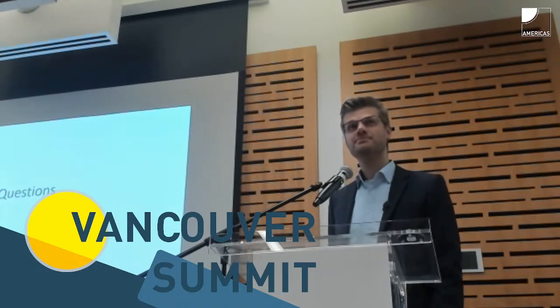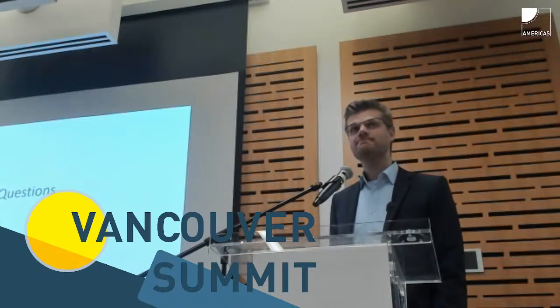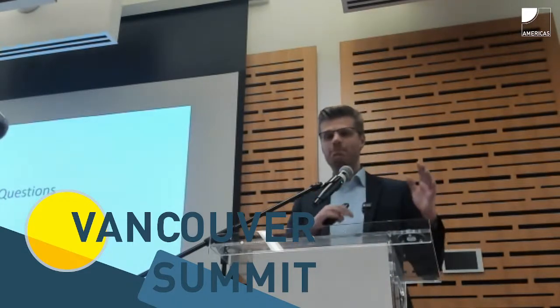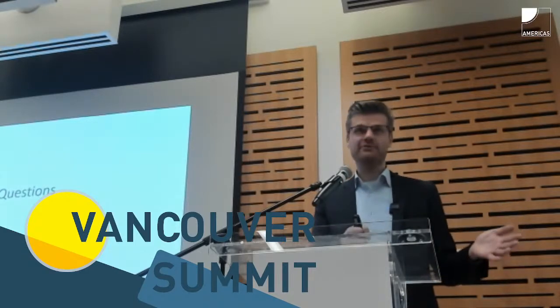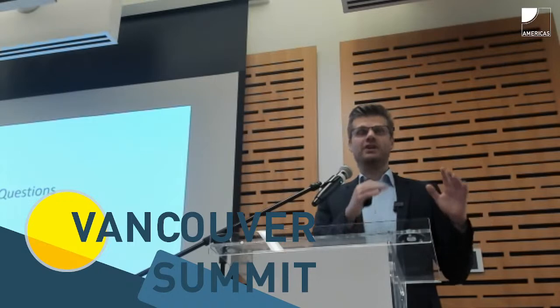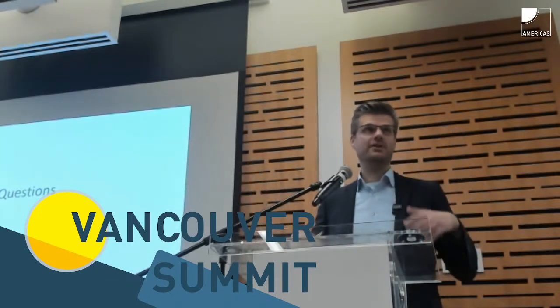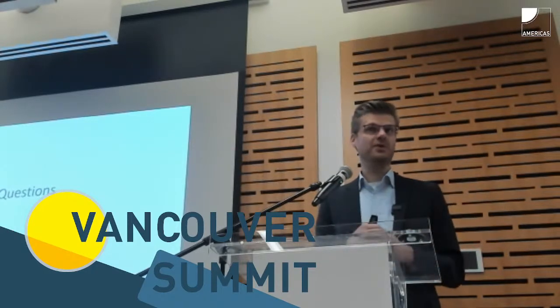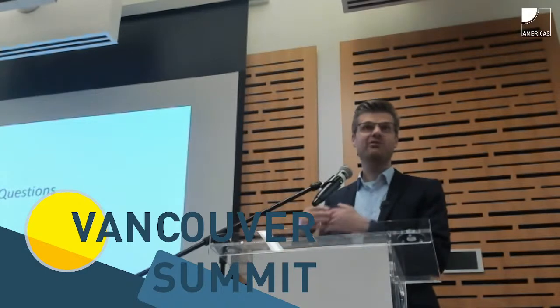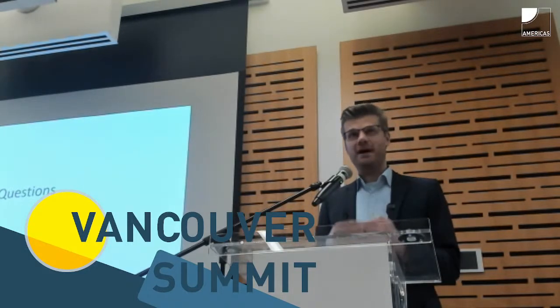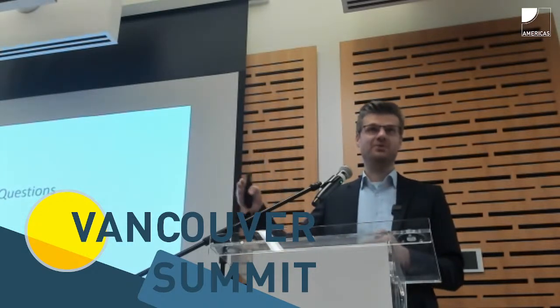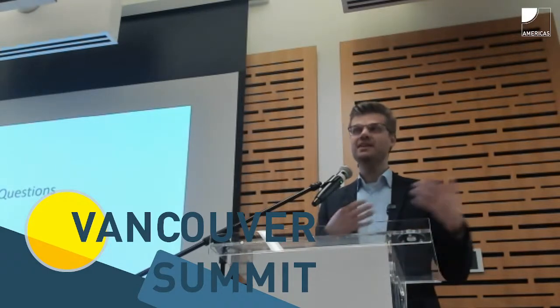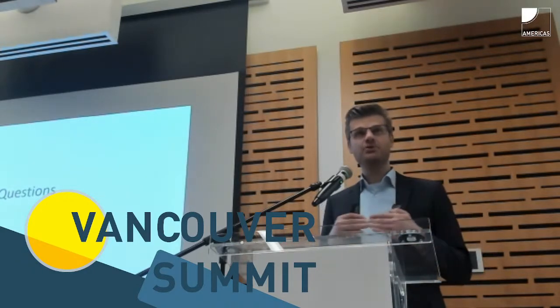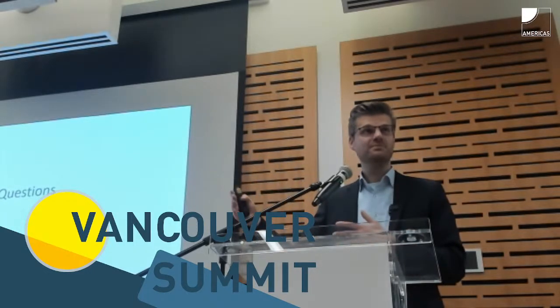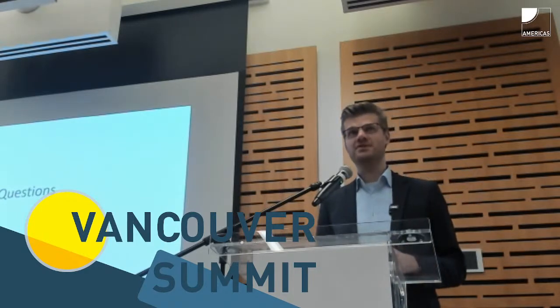Yeah. Just a quick question. What do you feel about a high voltage battery and a low voltage battery? So we see a shift in the industry, specifically for North America. Most manufacturers came from a low voltage application, typically 48 volts, because all the inverters that were already certified and on the market and people knew, from the Schneider Electrics to the Outbacks to whichever brand you look at, are all low voltage, because the code just until recently had a 50 volt battery limit. And now that battery voltage limit has increased for residential dwellings to 600. So that was the initial issue, that you could not have a high voltage battery in your residential dwelling. So now the battery voltage is similar to the residential PV voltage at 600 volt DC, so you can also have a 600, or up to 600 volt DC, battery system in your house.